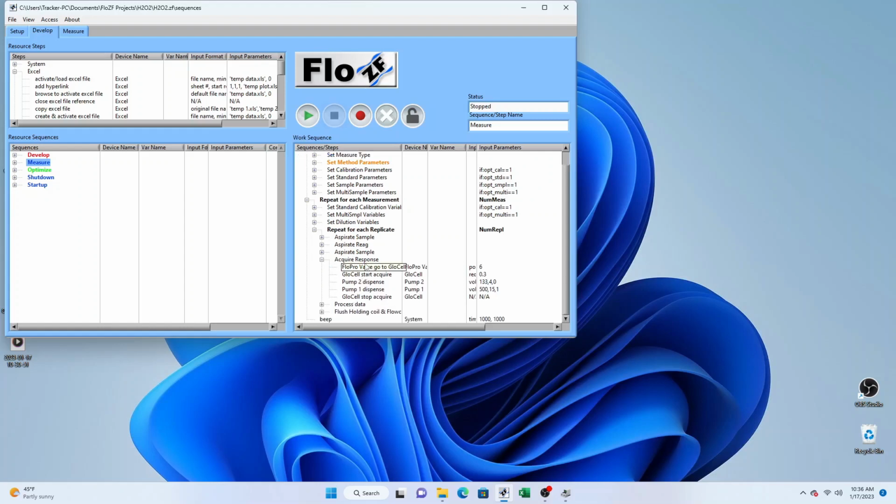During this acquisition phase, the second pump is used to merge a second reagent in with the reagent stack that we've built into the detector, and while those pumps are running, we acquire data. Once they stop running, we end the data acquisition.